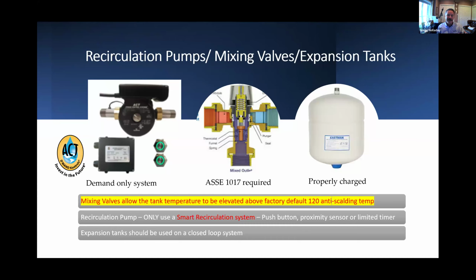Recirculation systems, every manufacturer is on the same page when it comes to recirc. We don't mind using a recirc as long as it's a smart recirc. A smart recirc has a button that says it's now 6 in the morning, time to take a shower. My wife steps in, pushes the button, and in about 15 seconds, my demand system that you see right here, this ACT system, circulates 70 feet of water line. When she turns the shower on, boom, it is steaming hot water right there at the shower.